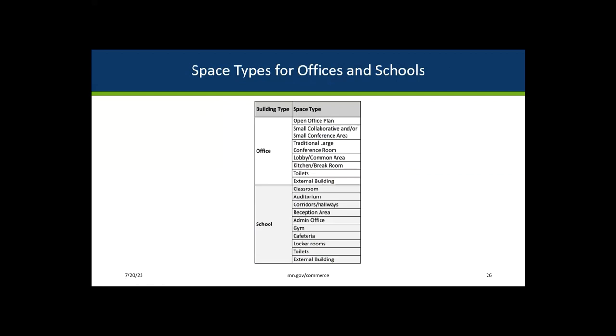Now that we understand the equipment costs and energy loads for network systems, we needed to evaluate the appropriate level of intelligence for different space types. Buildings are composed of a number of different space types, which will have their own uses and operational needs. This table shows the range of spaces typically seen in office and school buildings. We then identified typical needs and functionality for each. For example, an intelligent lighting system in an open office area of cubicles could benefit from more individual luminaire control than the lights in a conference room or a lobby.